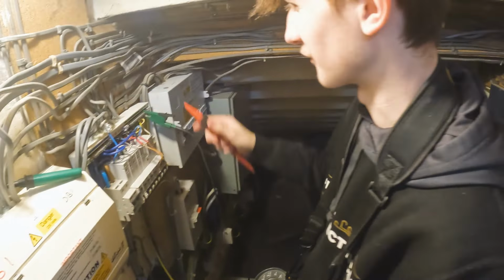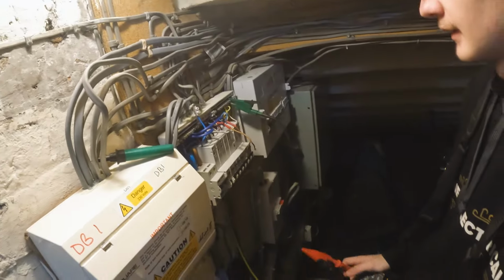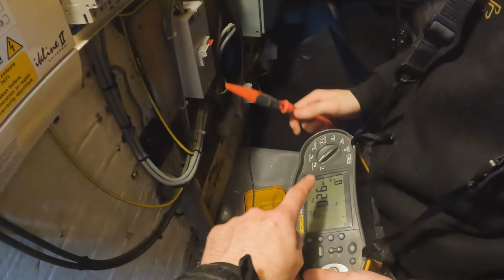Right, so it's both circuits. It's both circuits we've got to look into basically. So let's dive into these circuits. We will test the RCD as well, but this showing a bad result is indicating that it's most likely the circuit rather than the RCD.